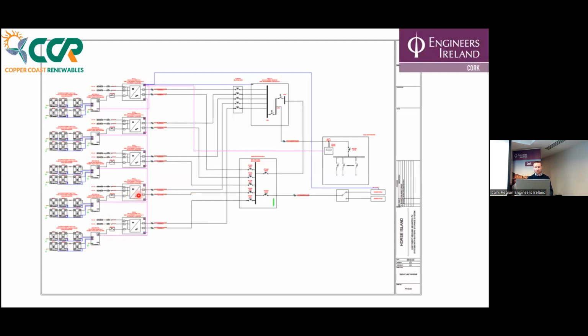Now this is where it starts to get a bit confusing. Off every inverter there's a dual feed, one to a normal board and one to an essential power services board, an EPS board. Under normal designs, batteries only provide essential loads. The problem with an island setup is everything is essential, there's no grid, so the loads can't just operate without power.